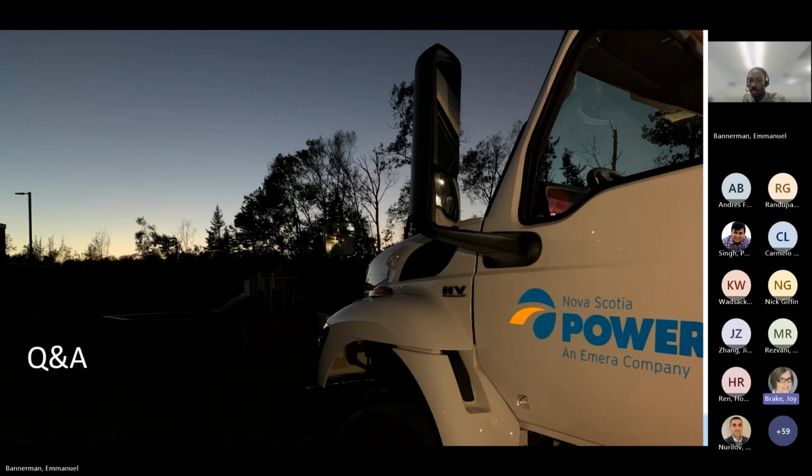Experience in using generic model and tuning the model to represent IBRs. It's not bad. Whether it matches field data, when we have those generic models in the big case, and there's only a certain percentage, like it's less than half, it doesn't put a significant impact on the results. I cannot say what would happen if we ran the full system with all generic models and then benchmarked against field data. So our field data has been based on our case, which does have some generic models because that was available. We did do large-scale models in about 2018. When we put the HVDC link in, that case had pretty well all generic models, and the results were reasonably comparable.